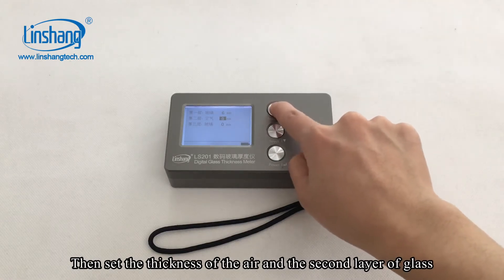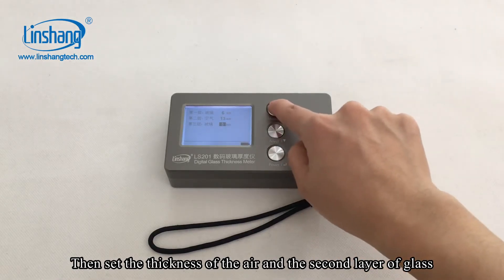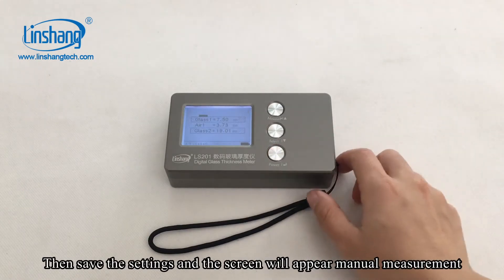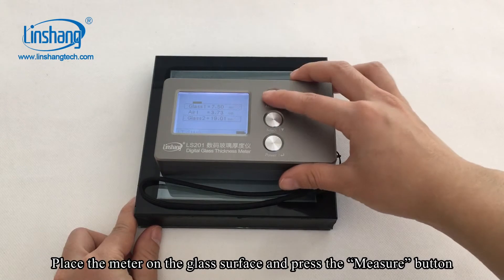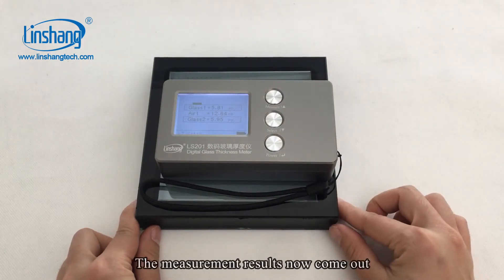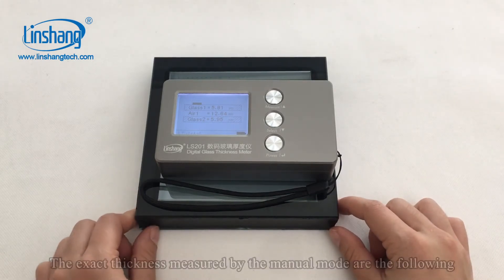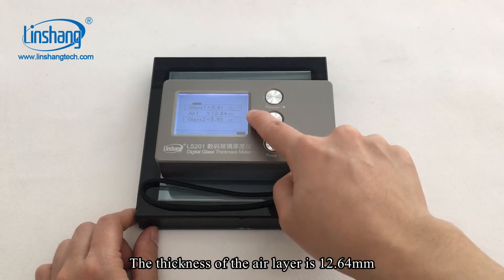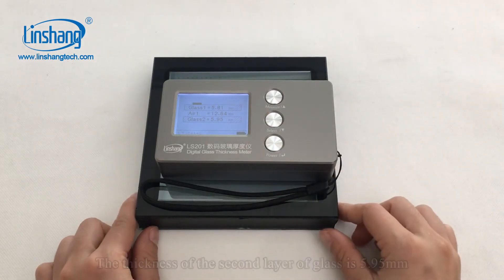Then set the thickness of the air layer and the second layer of glass. Save the settings and the screen will display manual measurement. Place the meter on the glass surface and press the measure button. The measurement results come out. The thickness of the first layer of glass is 5.81 mm, the thickness of the air layer is 12.64 mm.